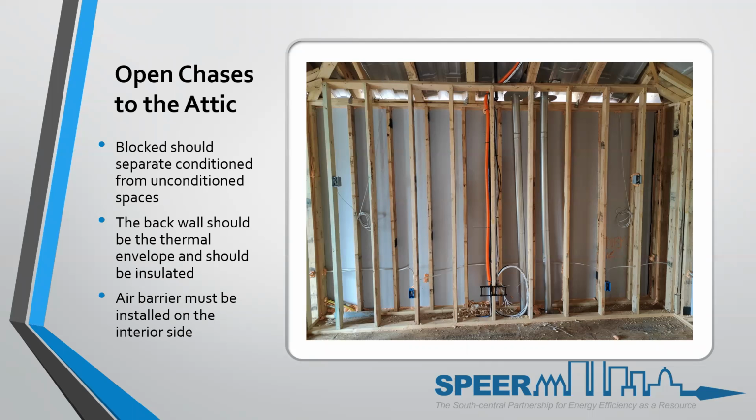So here, again, you'll probably see this in future webinars. It's just something that I can't believe was still done. And from what I saw when this house was being built, it was never corrected. It was insulated on the back. It was netted in front of that insulation. And then it was batted on the top with netting holding the bats in place. There is no air barrier at the top. I don't know how this house is going to get through on a blower door.